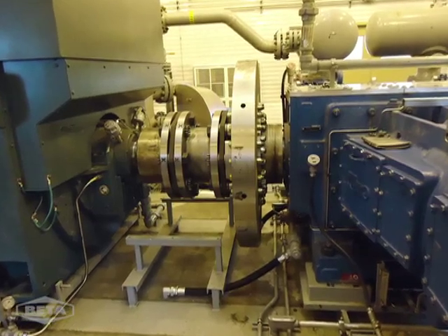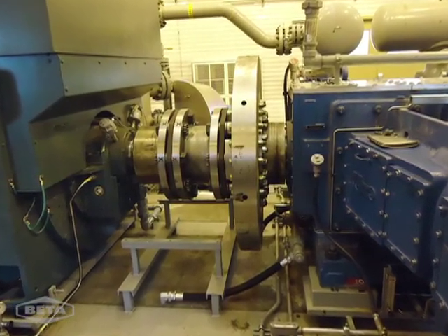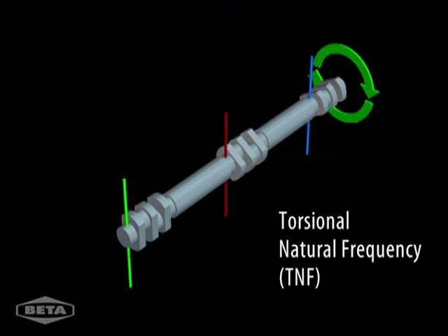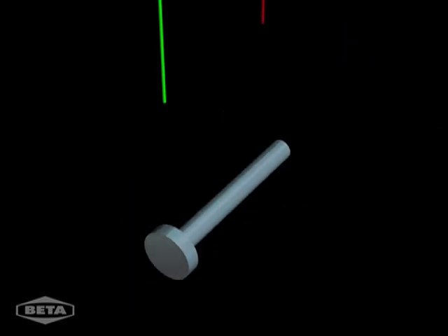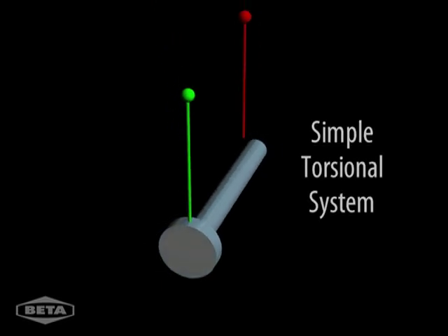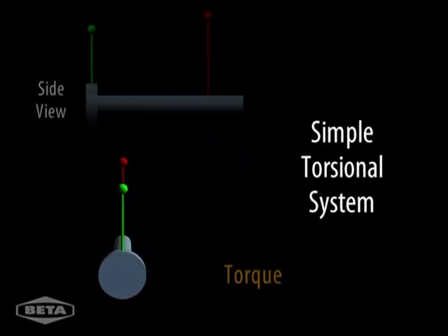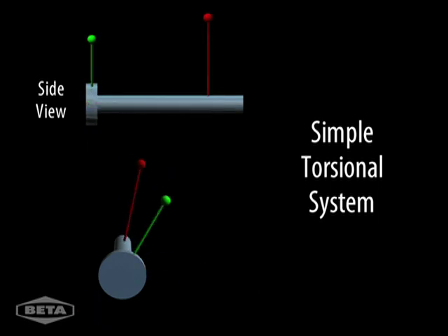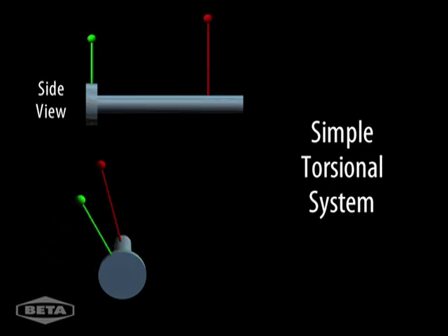A complete drivetrain or torsional system — for example, a reciprocating compressor with a coupling and an electric motor — has a torsional natural frequency, or TNF. Torsional natural frequency is defined as the frequency at which a shaft twists back and forth. Imagine twisting a shaft by rotating one end.